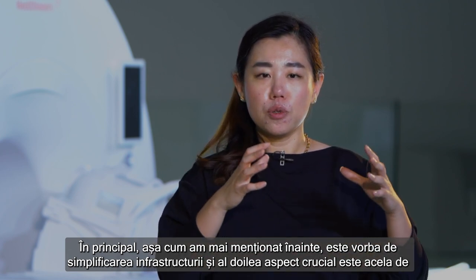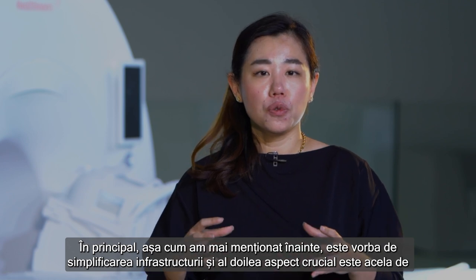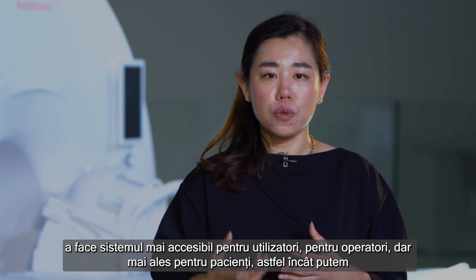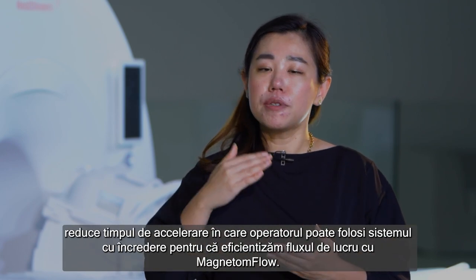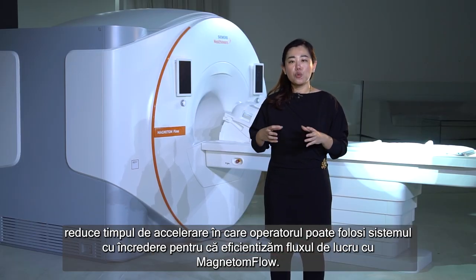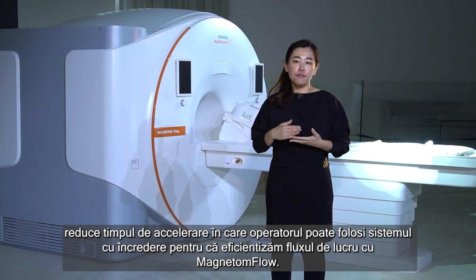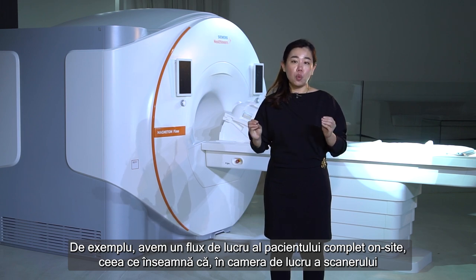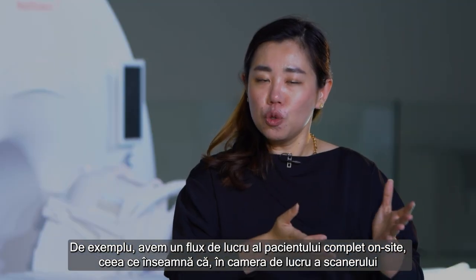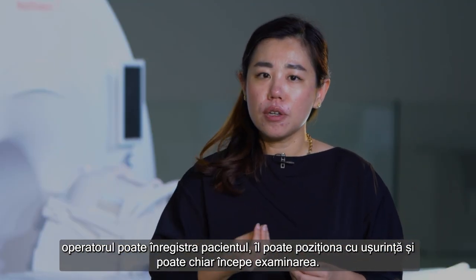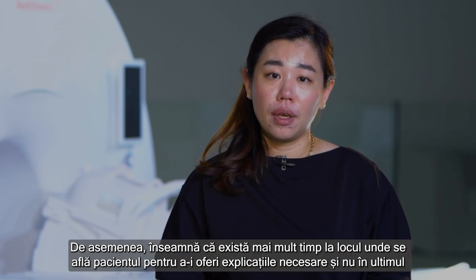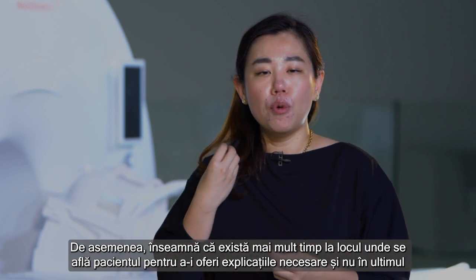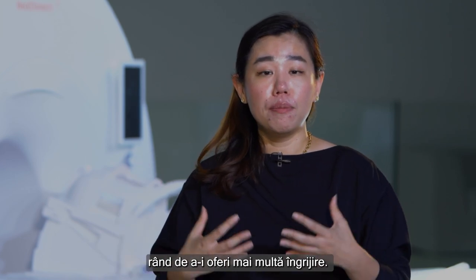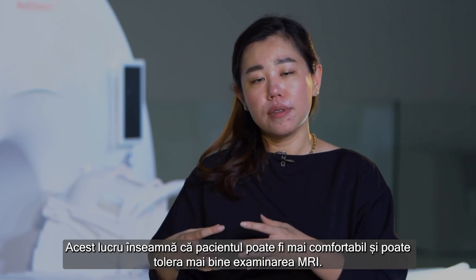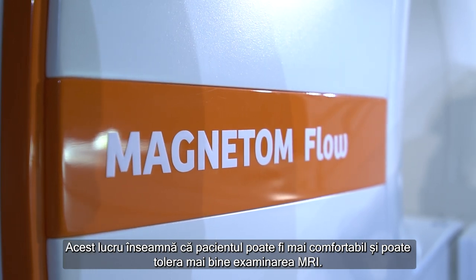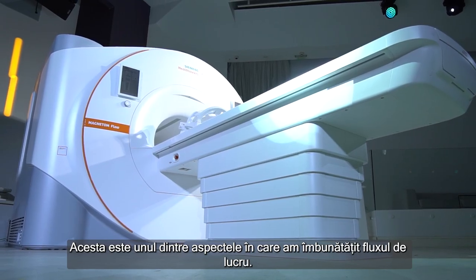First, like I mentioned before, is to simplify the infrastructure. The second crucial part is to make the system more accessible to operators, to users, and to patients. We can reduce the ramp-up time so the technician can use the system confidently, because we streamline the workflow efficiency with the Magnetom Flow. For example, we have a complete patient-side workflow, which means right in the scanner room itself the operator can register, can position the patient easily, and can even start the examination. This means they have more time to explain to the patient, to provide more patient care, and the patient can be more comfortable and tolerate the MRI examination better. So this is one aspect where we improve the workflow.